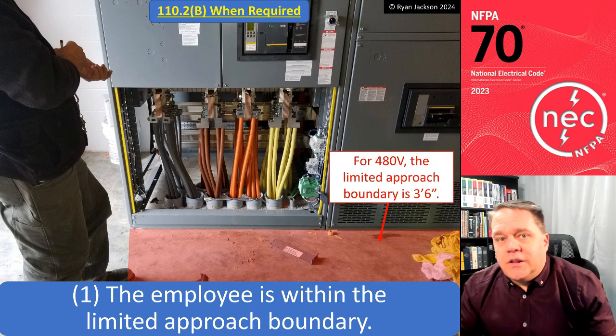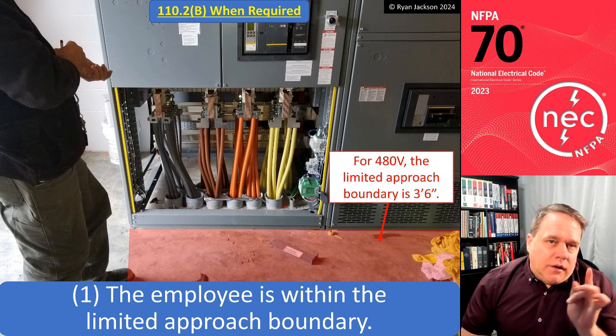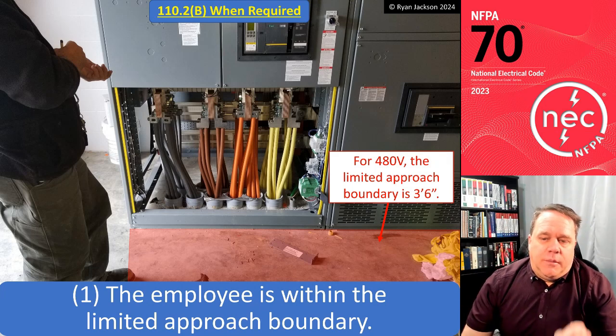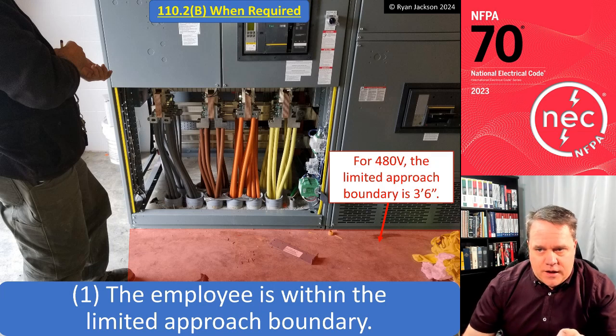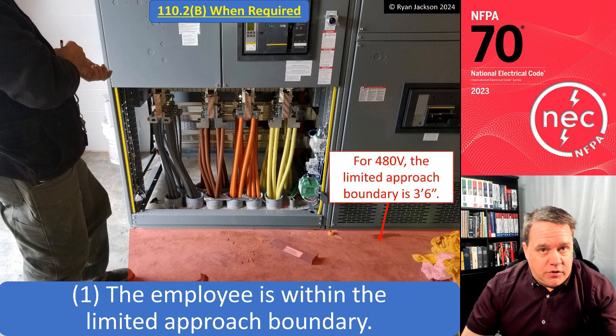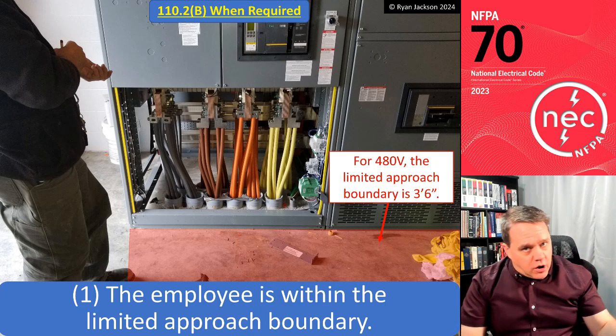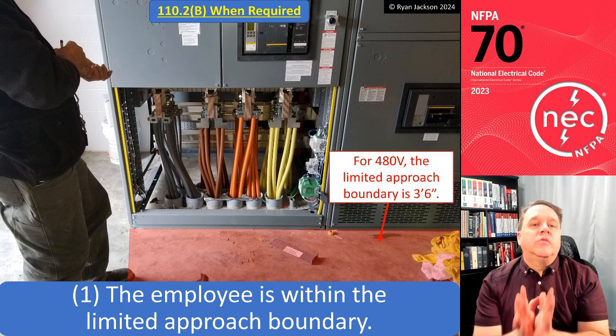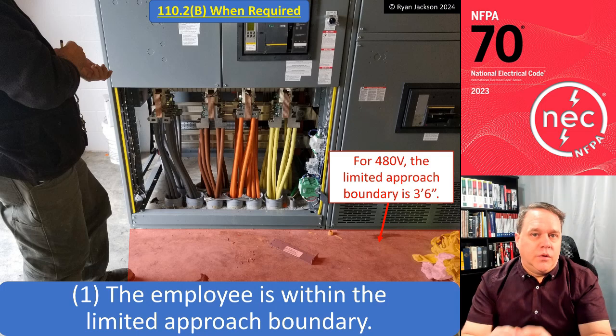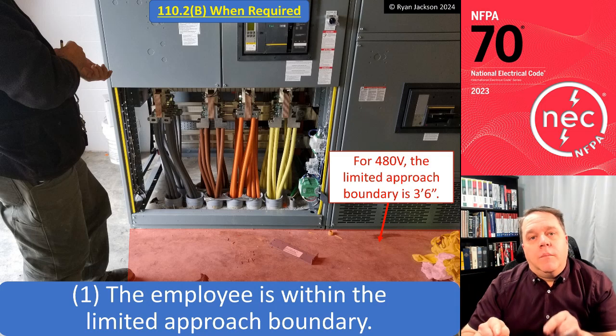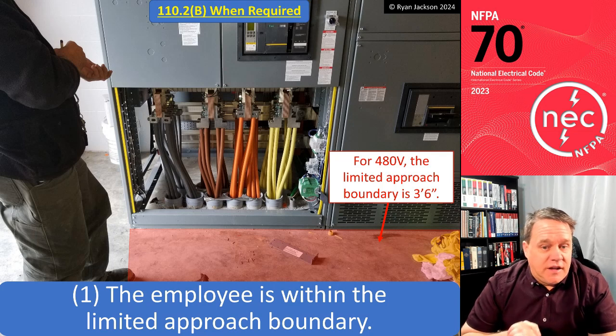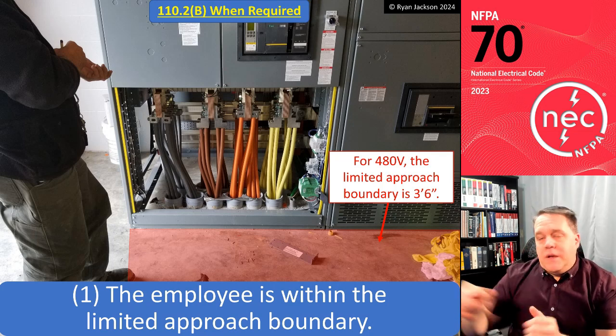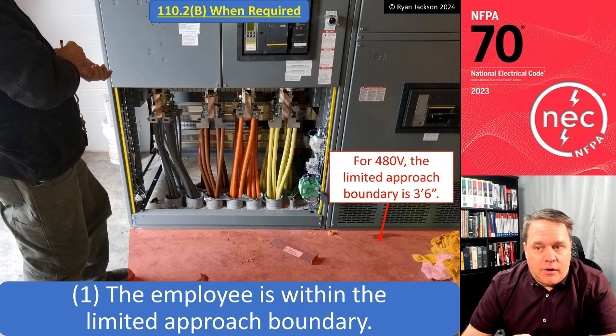We have to have an electrically safe work condition if the employee is within the limited approach boundary. Now, with the cover on, there is no limited approach boundary, right? It's with the cover off. So if I have exposed live parts and I'm within 3.5 feet of them, that equipment needs to be in an electrically safe work condition unless we meet the exception that we're going to talk about.